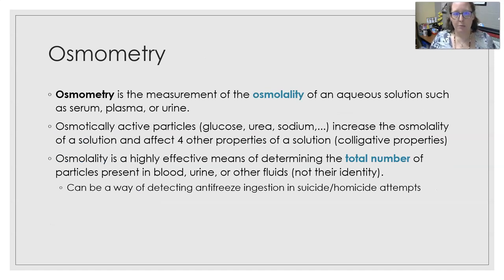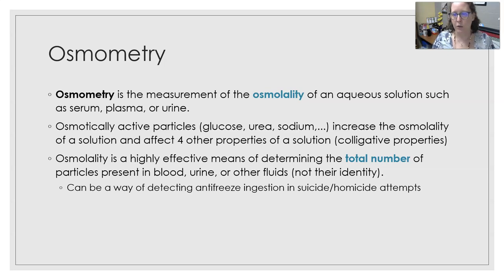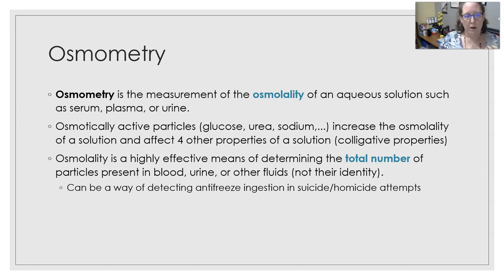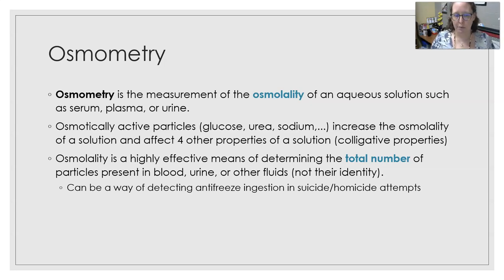Osmometry is a measurement of the osmolality of an aqueous solution, such as serum, plasma, or urine. Osmotically active particles such as glucose, urea, and sodium will increase the osmolality of the solution and affect the four colligative properties. Osmolality is a highly effective means of determining the total number of particles present in blood, urine, or other fluid — but not the identity of those particles.